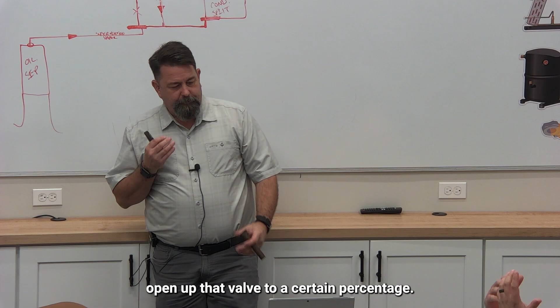This device is called an analog output module, AOM. Most of our outputs with Novar or Emerson or Danfoss are digital. They're on or off, open or closed. But what if we want to send a percentage? That's an analog output. So this is how Novar does it with an analog output. Once again, this will send 0 to 10 volts DC or 4 to 20 milliamp, doesn't care. It'll do either one. But it can tell something to go to a percentage.